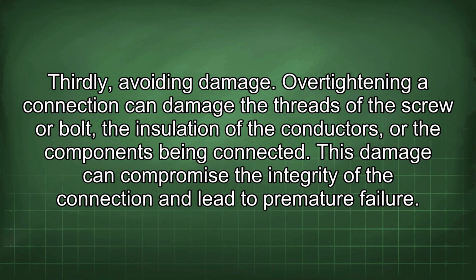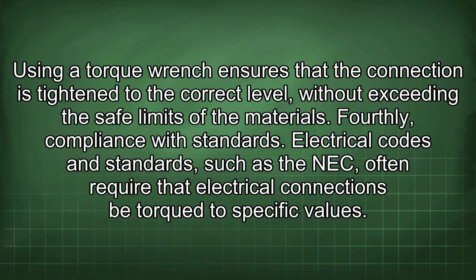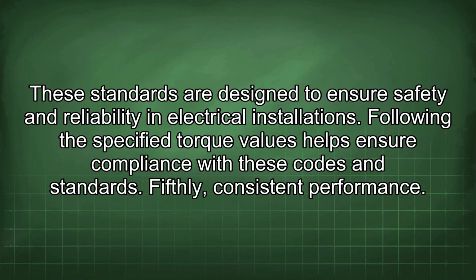Thirdly, avoiding damage. Over-tightening a connection can damage the threads of the screw or bolt, the insulation of the conductors, or the components being connected. This damage can compromise the integrity of the connection and lead to premature failure. Using a torque wrench ensures that the connection is tightened to the correct level without exceeding the safe limits of the materials. Fourthly, compliance with standards. Electrical codes and standards such as the NEC often require that electrical connections be torqued to specific values. These standards are designed to ensure safety and reliability in electrical installations. Following the specified torque values helps ensure compliance with these codes and standards.